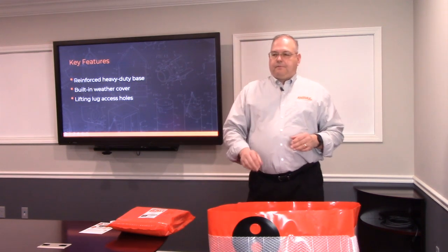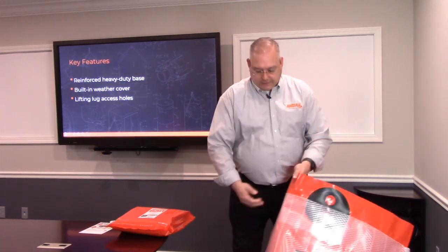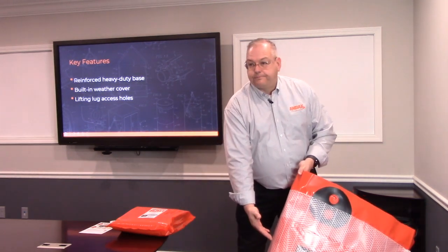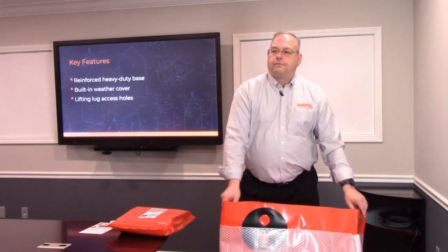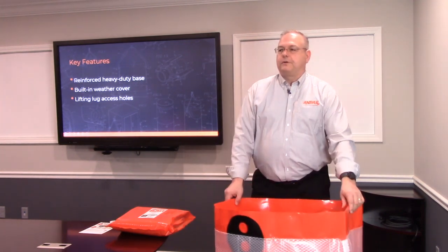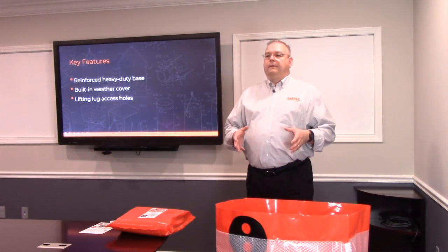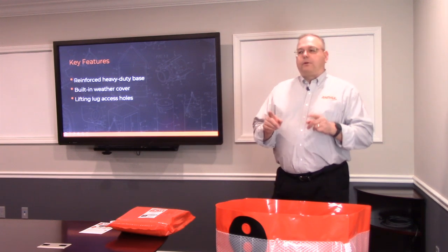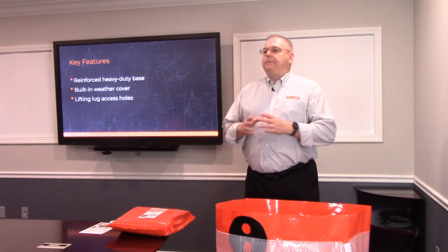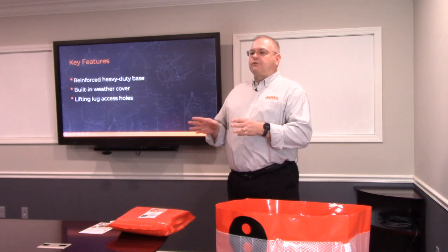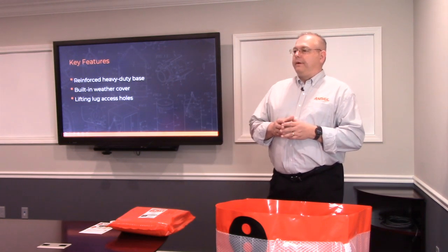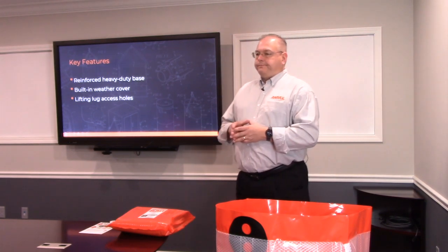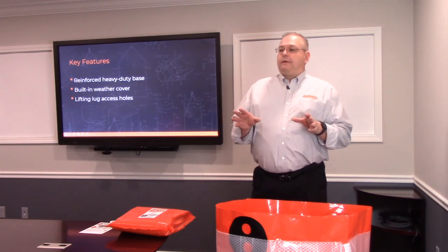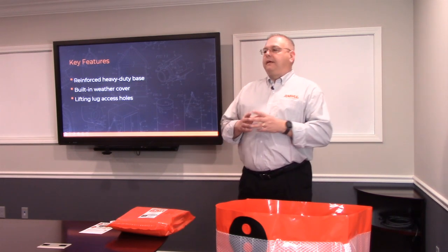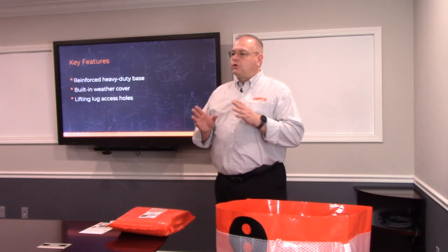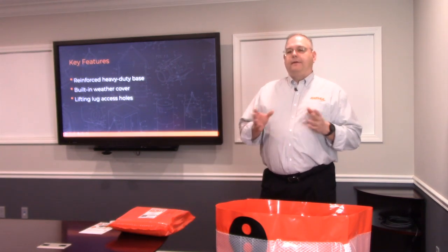The top of the TCB incorporates a clear reinforced weather cover. This cover is critical for your DOT compliance for transportation of a contained transformer. The cover, when deployed, seals the containment bag and prevents any drips, sprays, or leaks of oil while you're driving down the road. Additionally, it helps prevent the elements from entering the bag while you're transporting or storing the contained transformer in your utility yard.